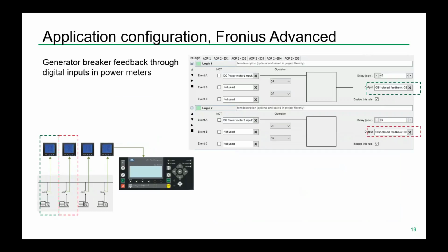We see applications also where there's a large distance, or just because it's easier and less expensive. Let's say your PV installation is on the roof and your generators are located in the basement, so you have some distance between them. So you can run a Modbus cable from the power meters. In this case I have 4 generators with power meters. I run Modbus to the DEIF controller where it is located. And then it's also practical, as you can see, to wire the generator breaker position into the digital power meters.